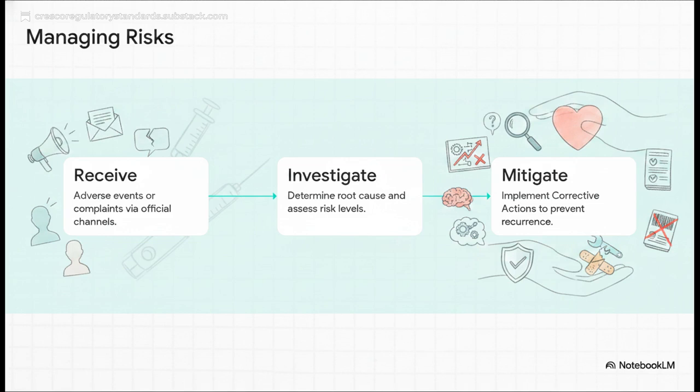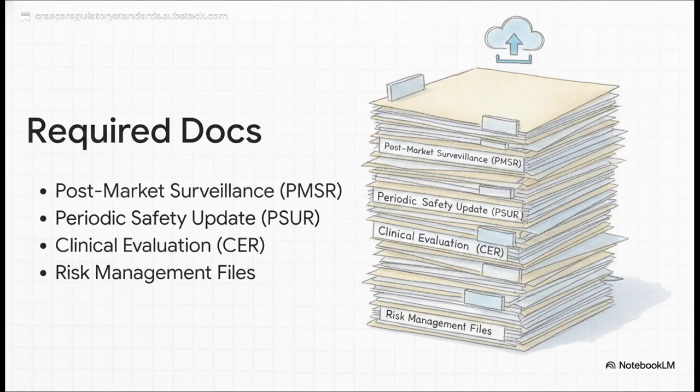They ensure field safety corrective actions, or FSCAs, are rolled out. This could be anything from recalling a bad batch to updating instructions, all to prevent recurrence and protect patients. Now, to support all this investigation, manufacturers have to do some serious heavy lifting. Through the official GHAD platform, they are required to submit extensive technical documentation. We're talking post-market surveillance reports, periodic safety update reports, clinical evaluation reports, and massive risk management files. Basically, they have to prove on paper that they are actively and continuously assessing the risks of their devices.